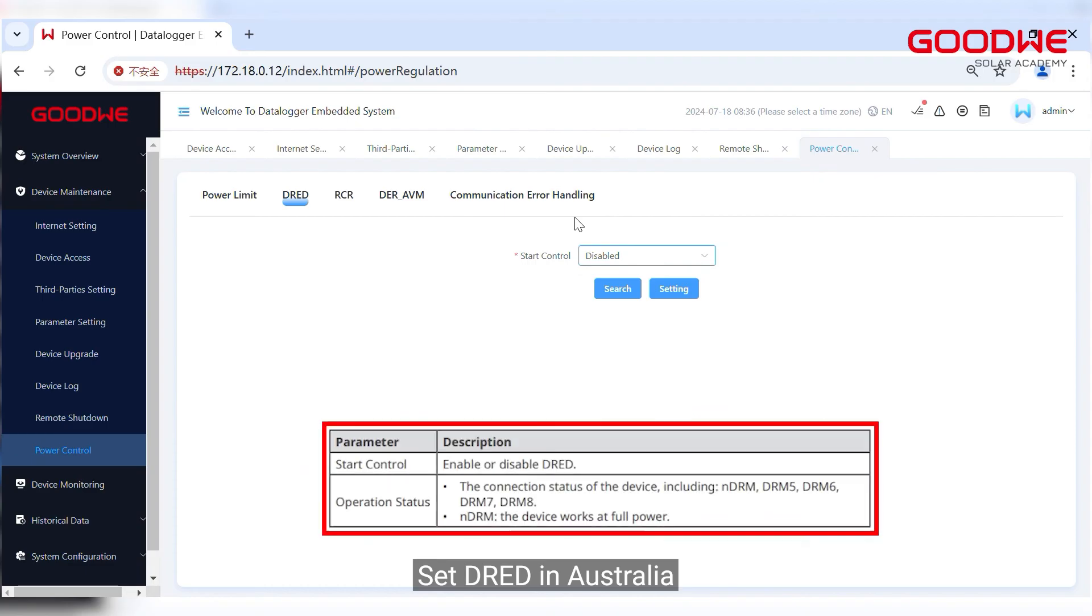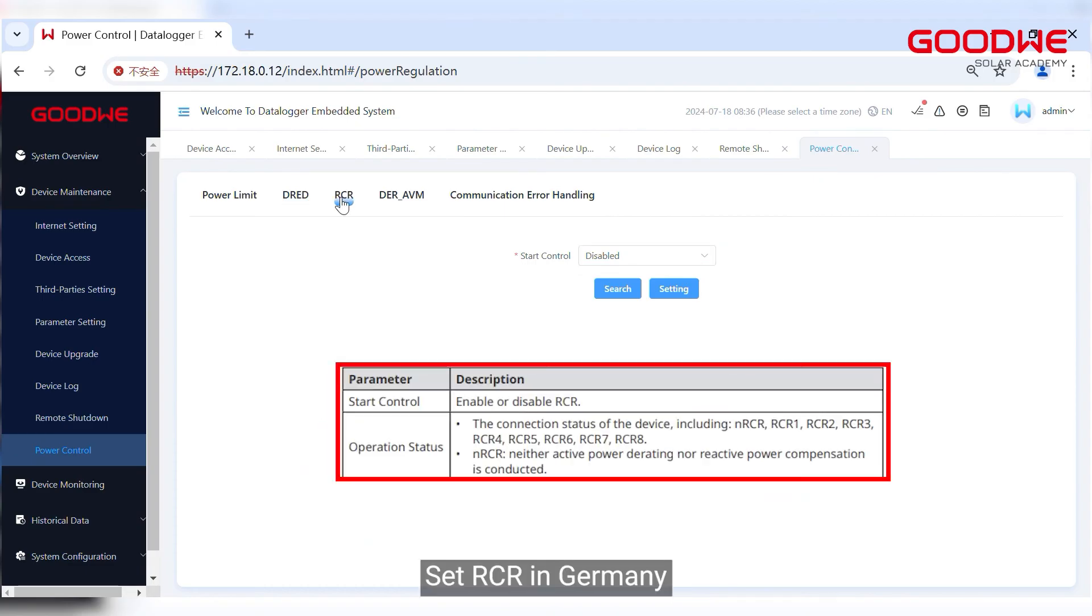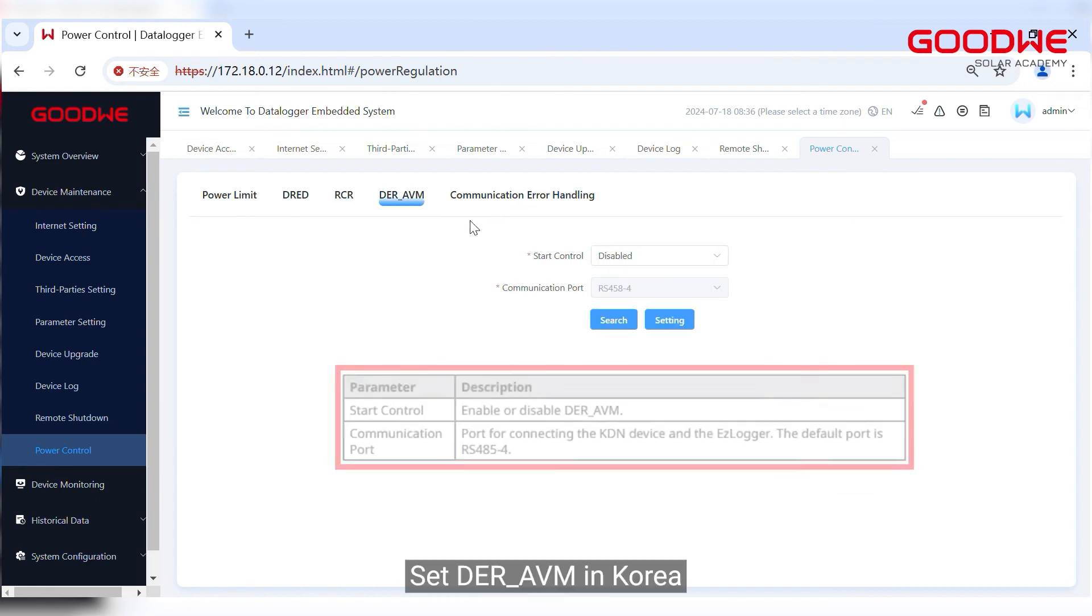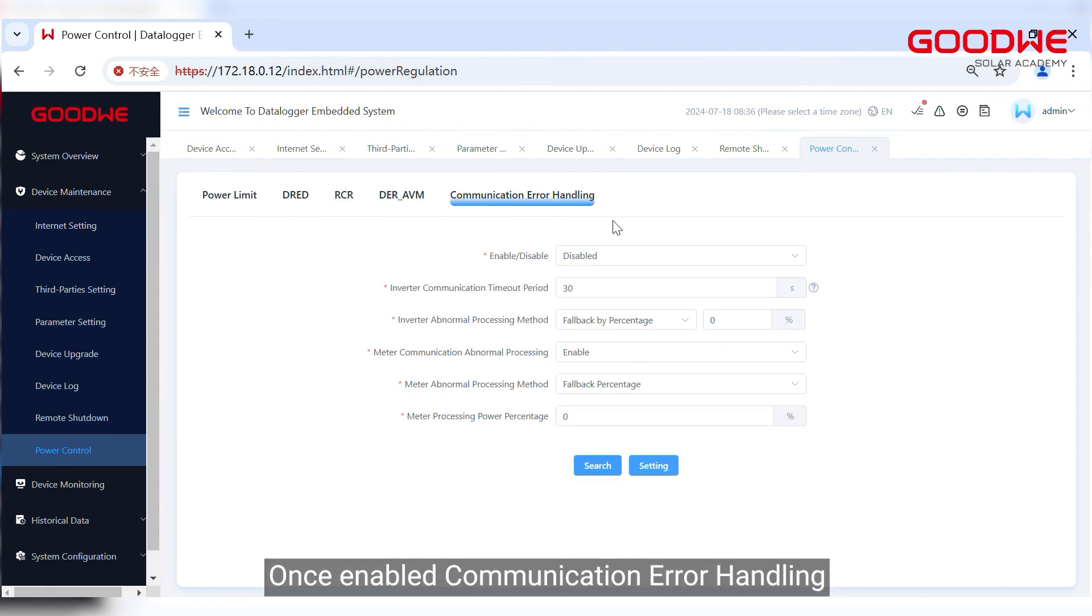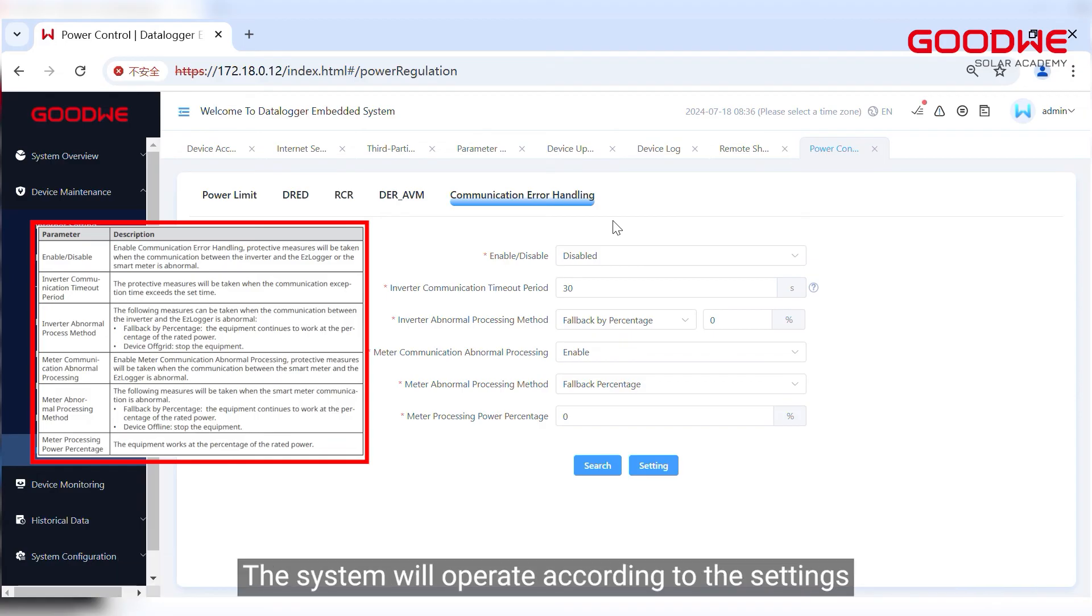Set DRED in Australia. Set RCR in Germany. Set DER_AVM in Korea. Once enabled communication error handling, if the communication between inverter or meter and logger is abnormal, the system will operate according to the settings.